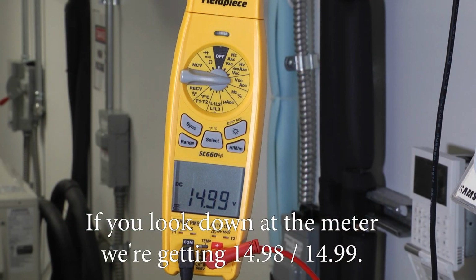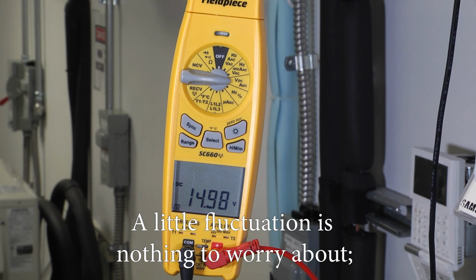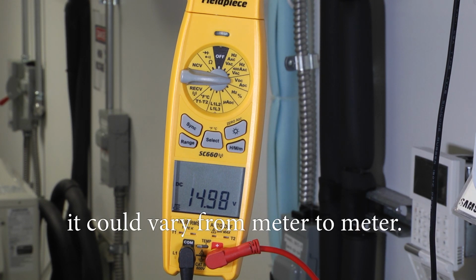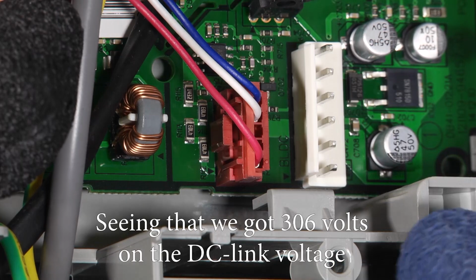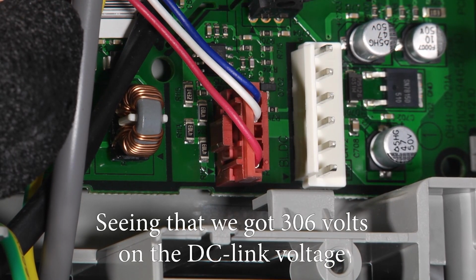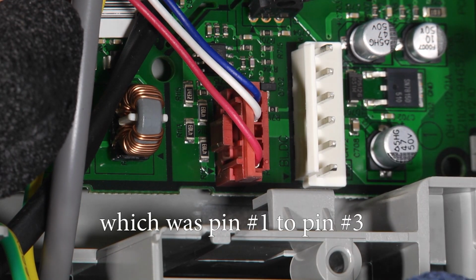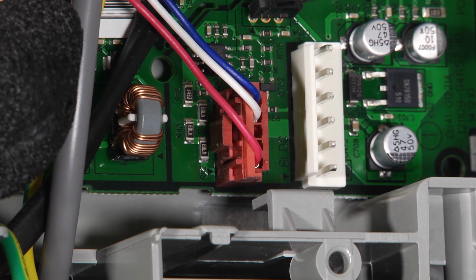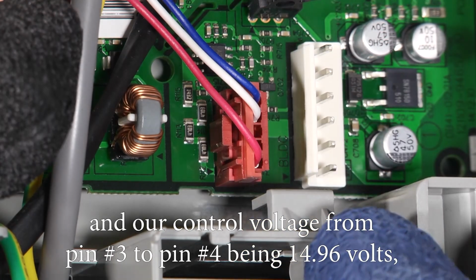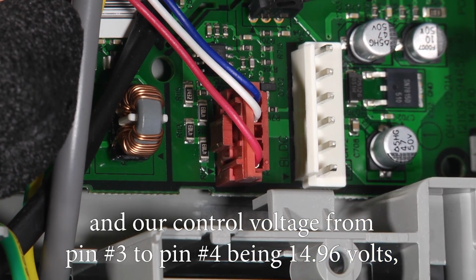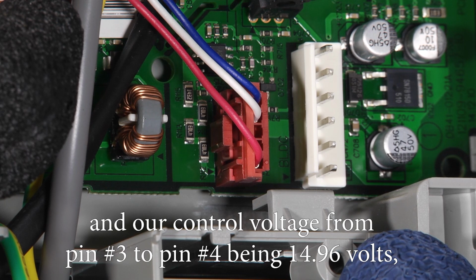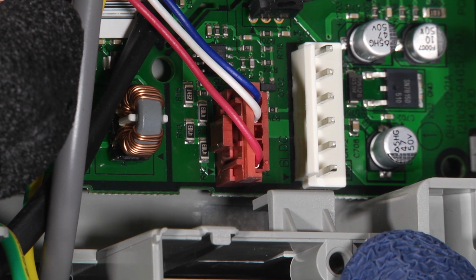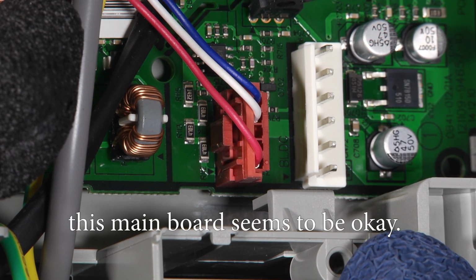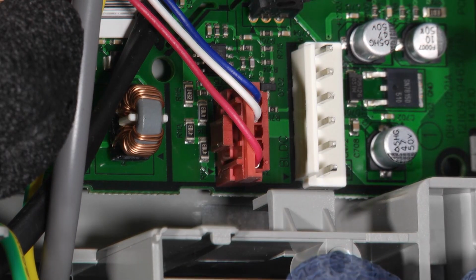If you look down at the meter, we're getting 14.98 / 14.99. A little fluctuation, nothing to worry about, it could vary from meter to meter. Seeing that we got 306 volts on the DC link voltage, which was pin number 1 to pin number 3, and our control voltage from pin number 3 to pin number 4 being 14.96 volts, this main board seems to be okay.